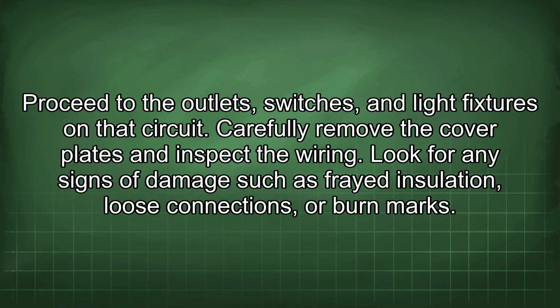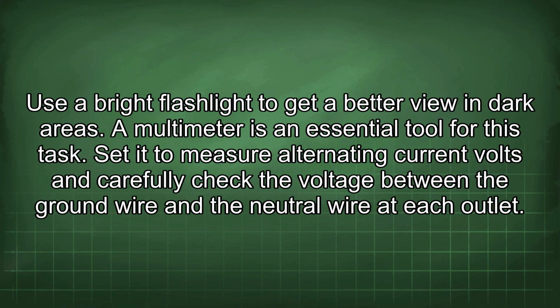Proceed to the outlets, switches, and light fixtures on that circuit. Carefully remove the cover plates and inspect the wiring. Look for any signs of damage such as frayed insulation, loose connections, or burn marks. Use a bright flashlight to get a better view in dark areas.